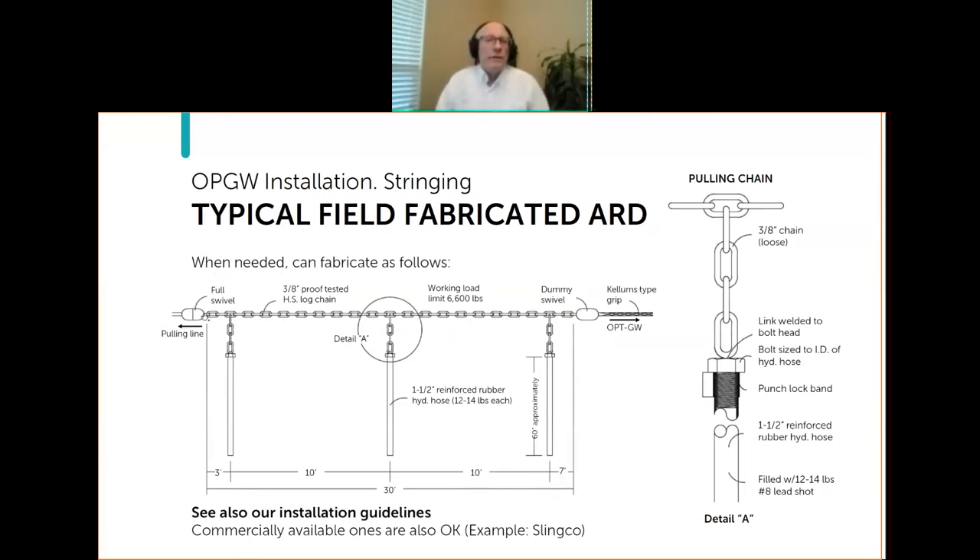A typical anti-rotation device can be fabricated in the field with chain using the dimensions provided. As the cable gets larger, we might have you increase the weight a little. These are also in our installation instructions. Commercially available ones exist — Slingco has one, for example. Contact the cable manufacturer to make sure you're using an anti-rotation device that's proper for the cable you're trying to install.